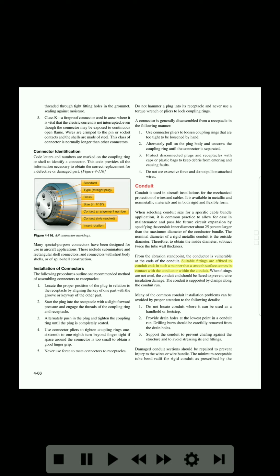Suitable fittings are affixed to conduit ends in such a manner that a smooth surface comes in contact with the conductor within the conduit. When fittings are not used, the conduit end should be flared to prevent wire insulation damage. The conduit is supported by clamps along the conduit run. Many of the common conduit installation problems can be avoided by proper attention to the following details.